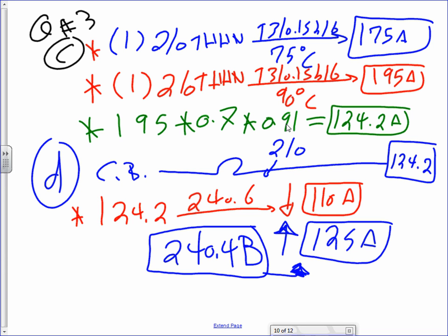Except if you're using assemblies where you're plugged in, like for example, receptacles like these. If I have a branch circuit and I'm feeding all these receptacles, I can't go up, because people can increase the load and plug the load in at any time. If I'm feeding a panel, then I can go up. So for the test, if you go down, that's fine with me, but to understand it fully as we move through, this is what applies, 240.4(B). But for example, this one most likely is going to be a panel, and we go up. Do you see a receptacle fed from a 2 AWG?